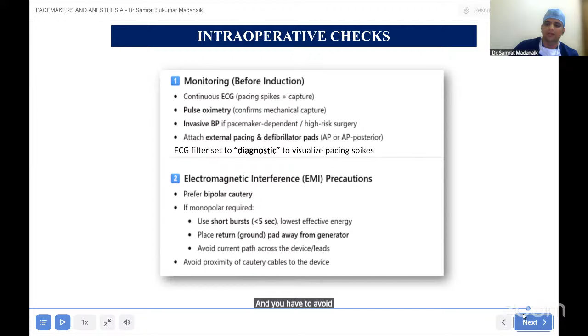Device management during surgery. Remember, if the patient is pacemaker dependent, turn it to asynchronous mode, that is the DOO or VOO mode. If this is possible in elective surgery, get a technician to set it to asynchronous mode. If it is emergency surgery, just apply a magnet and it will get converted to asynchronous mode, and keep a watch on the ECG. In case of ICDs, remember, applying a magnet is just going to turn off the anti-tachycardia function, and an external defibrillator must always be connected to the patient. The pacing mode is never changed when you apply a magnet in patients with ICDs.